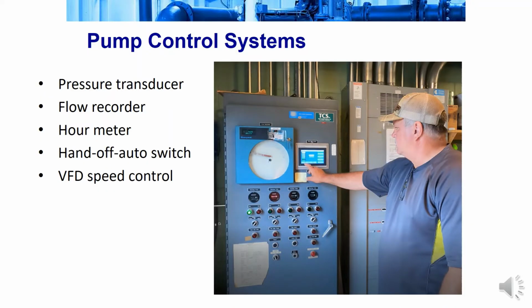This next section, Bob Lawson talks about the pump control systems for the Portage wastewater lift station. These pump control systems include the pressure transducer, the flow recorder, an hour meter, the hand off and auto switch, and the variable frequency drive speed controller for the pump motors.